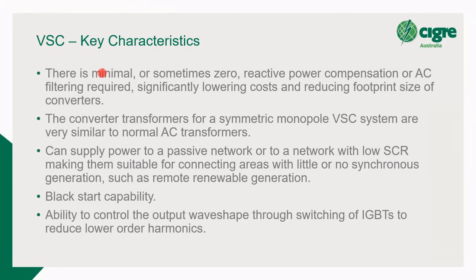Okay, so key characteristics of VSC. Why do we like it, and what are some of the disadvantages? Minimal reactive power compensation is required, so there is lower cost and a much smaller footprint for your converter. So you can fit these converters into pretty neat places, which is one of the reasons, not the only reason, why it's a technology suitable for offshore wind farms, for example. But also if you needed to bring an HVDC system into a very heavily populated area like a city, VSC is ideal for that.